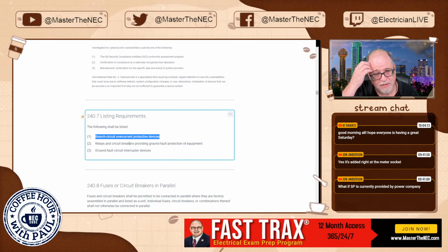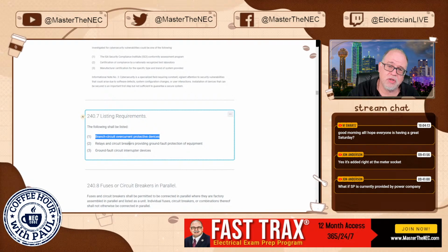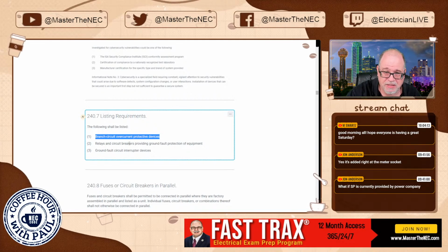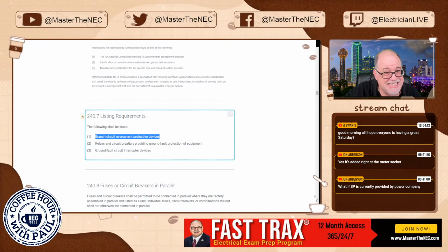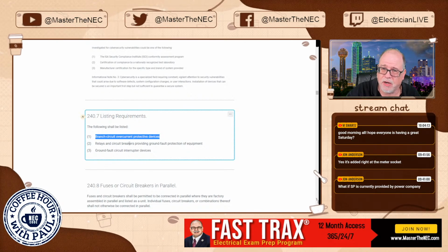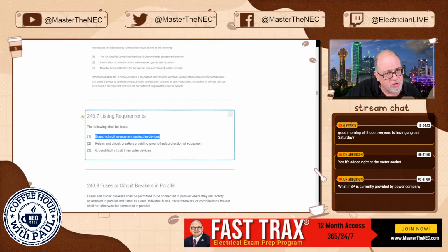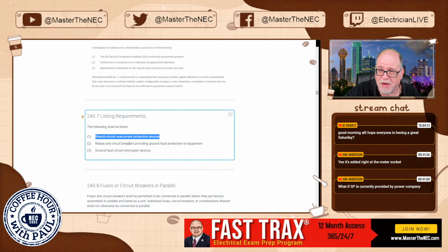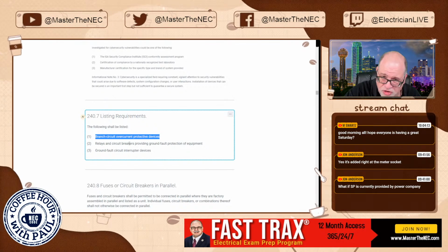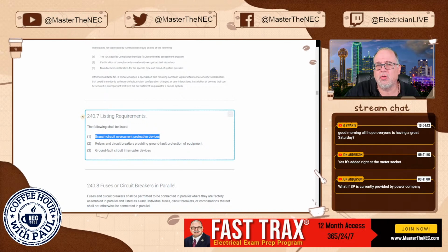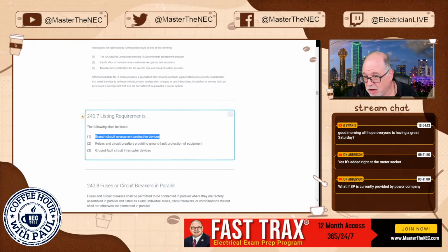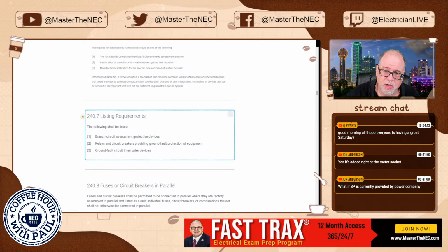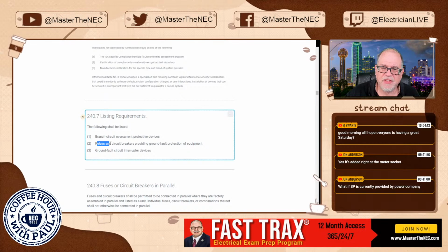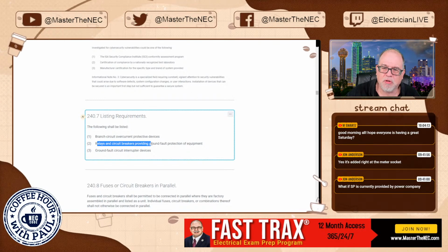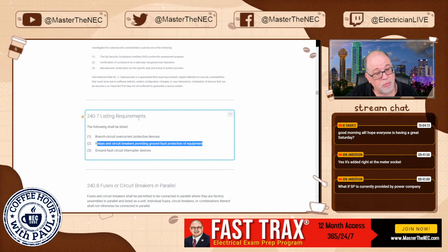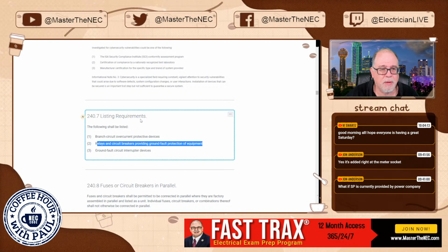Okay, and everybody asks me all the time, what's listed, what not? So the code will tell you what's required as far as the NEC to be listed, but there's also some applications of products that are identified for specific use that also are going to be under applications like 110.3(B). The instructions from the manufacturer might not have something to do with the listed product, but they're still going to give you direction on how it's to be installed. But when it comes to overcurrent protection, here is what is required to be listed. Branch circuit overcurrent protective devices, relays, and circuit breakers providing ground fault protection of equipment is required to be listed. So GFP of equipment required for listing.